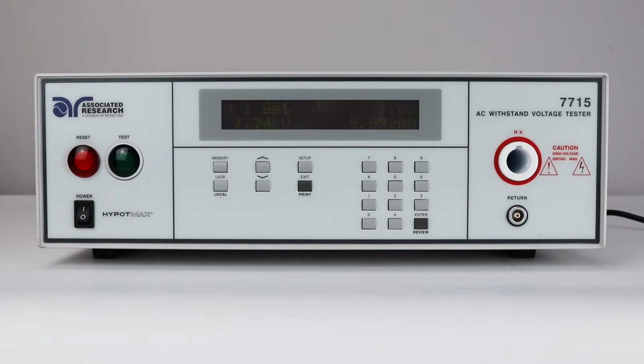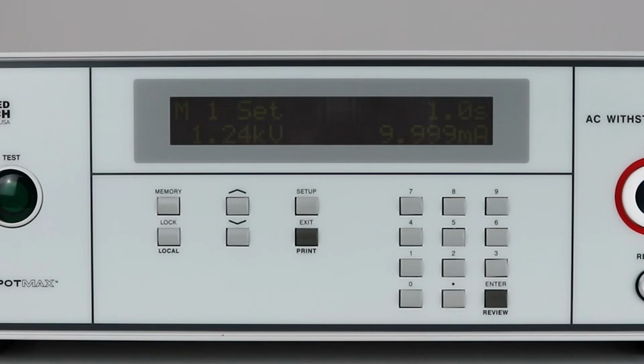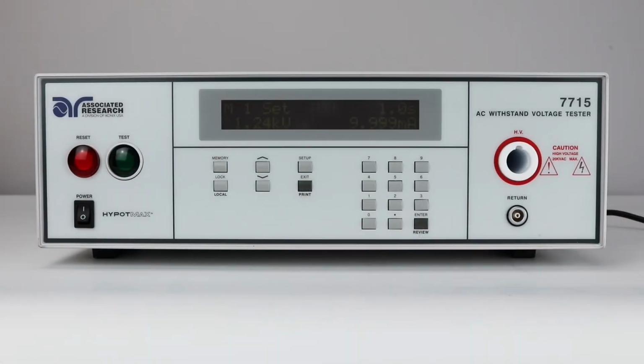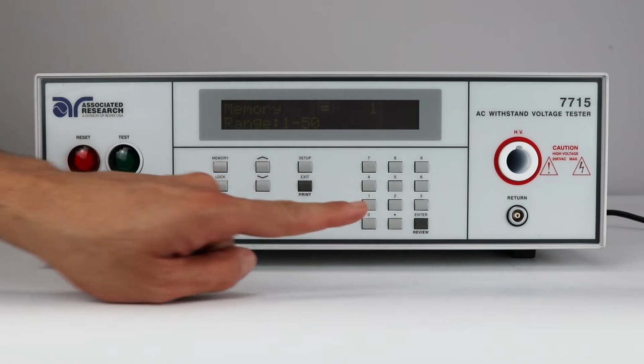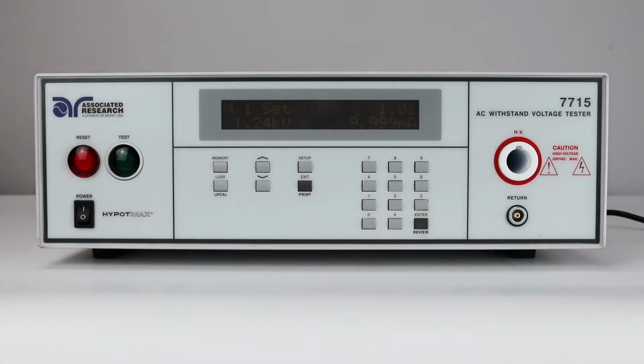The Perform Test screen displays 5 parameters: memory number, status indicator, test time, test voltage, and leakage current limit. First, we're going to set up an AC Hypot test in memory 1. Press the memory key, use the numeric keys to enter the memory location number, and then press the Enter key. For this video, we will use memory location 1. The program will recall the test parameter stored in this location and return to the operation mode automatically.